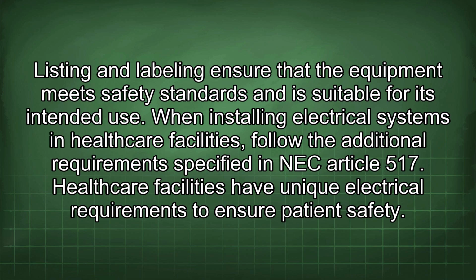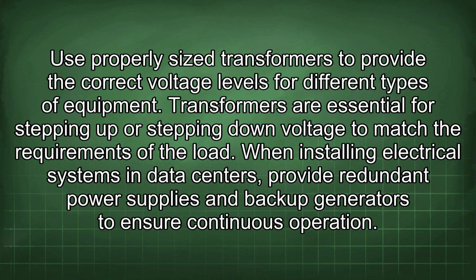When installing electrical systems in healthcare facilities, follow the additional requirements specified in NEC Article 517. Healthcare facilities have unique electrical requirements to ensure patient safety. Use properly sized transformers to provide the correct voltage levels for different types of equipment. Transformers are essential for stepping up or stepping down voltage to match the requirements of the load.